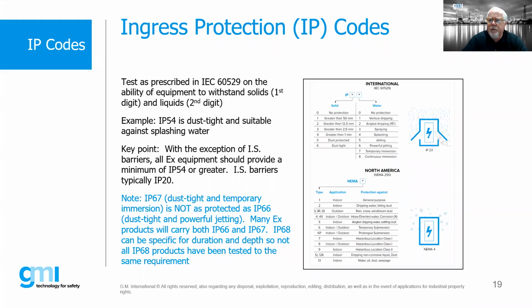Now, the other thing that's important to understand is what is called ingress protection, or IP code. Sometimes these are called international protection. But IP codes have to do with a piece of equipment and its suitability for an environmental condition. So there are generally 2 digits, sometimes followed by a letter, but generally speaking, there will be 2 digits. The first digit deals with solid protection. So this could be dust, this could be objects, some sort of solid, if you will.